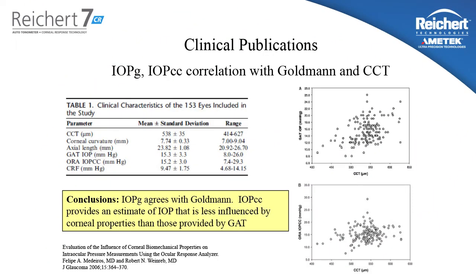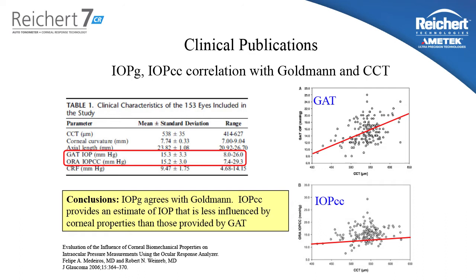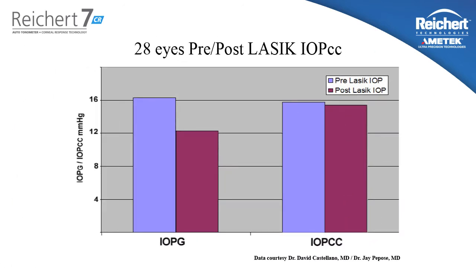This publication by Medeiros and Weinreb looked at the effects of corneal thickness on Goldmann tonometry and 7CR measurements. As you can see, the Goldmann tonometer is significantly affected by central corneal thickness, and the IOPCC measurement is not. Even though the IOPCC measurement and the Goldmann measurement agree with each other on average, the IOPCC measurement is not dependent upon corneal thickness.